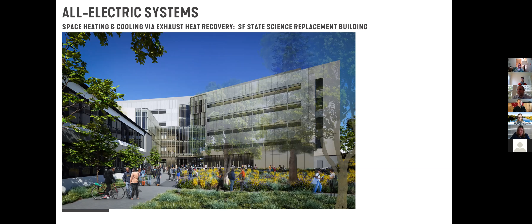So wet chemistry tends to have higher levels of exhaust required in the labs through the hoods, and that air exchange means that we have to make up that air. For all the air that we remove from the building, we need to bring that same amount of air back in, and that can present quite a heating load, or a demand for heating load. And traditionally, that's been provided by gas boilers that are heating a hydronic loop.